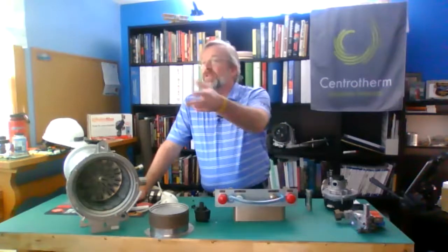All right, what do you got? Water coming into the boiler, into the heating side, not on the, well, even on the domestic. Is it recommended to put filters in and check pH and stuff like that? So 2 questions, but we'll answer them both together. pH, always important. Absolutely. pH and stainless, pH and copper, any of those things are just not friends. So it's at 7.5 to 9 range on your pH.